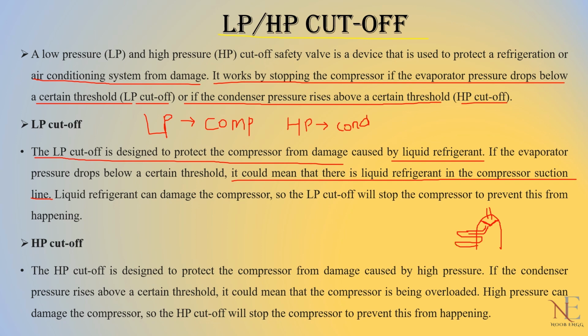Now the vapors go from here, while the baffles stop the liquid particles from going into the suction line. Now what does this LP cutoff system do? If liquid refrigerant enters the suction line, it would harm the compressor. It is not good when liquid particles are moving in the compressor. So as the pressure drops in the evaporator coils, the work of the LP is cutting off the compressor, meaning stopping it from working. This is the simple work of an LP cutoff system.